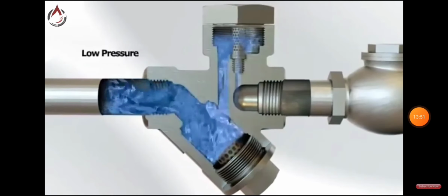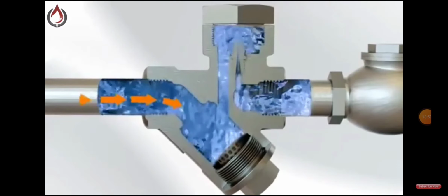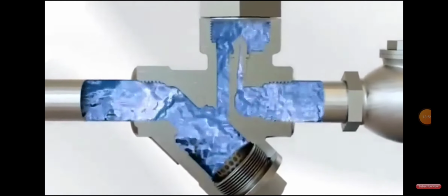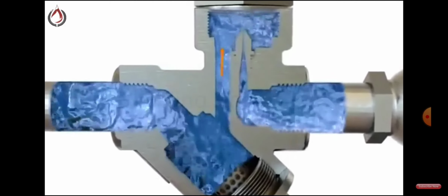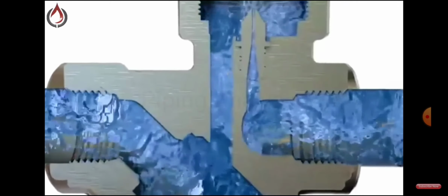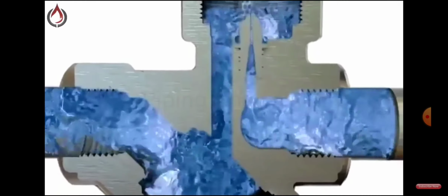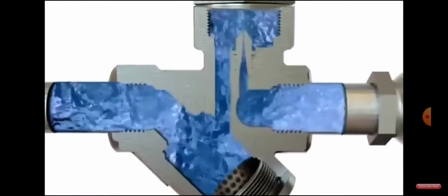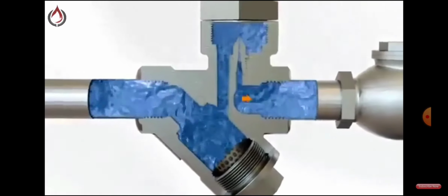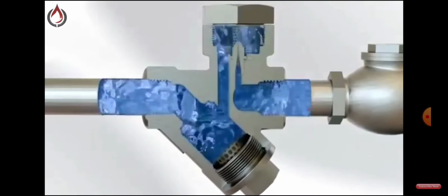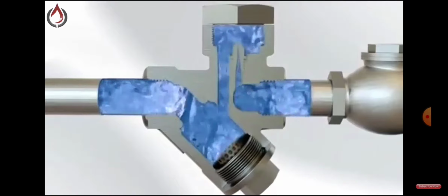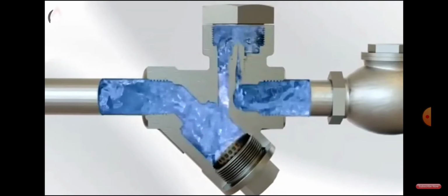At very low pressure and temperature, no flashing occurs as it exits the venturi. This means there is no back pressure present to restrict the flow of cold condensate as it exits the Delta trap. This cold water exits freely at 2 to 3 times faster than hot pressurized condensate can at running load. This absence of flash steam on startup is why Delta Venturi orifice steam traps are suitable for startup loads.